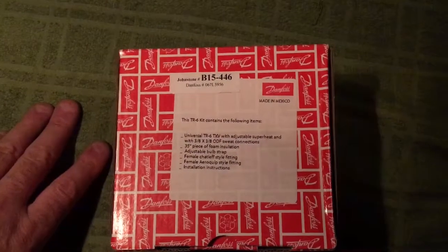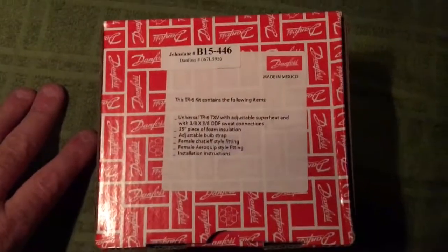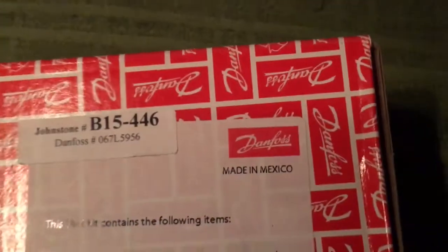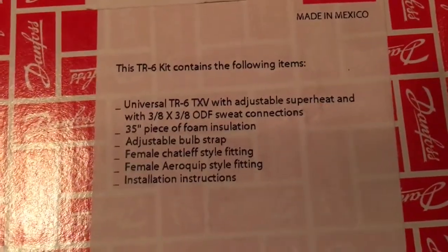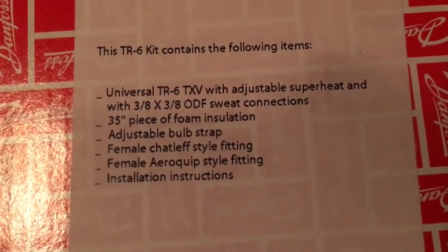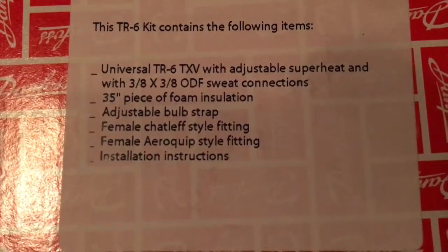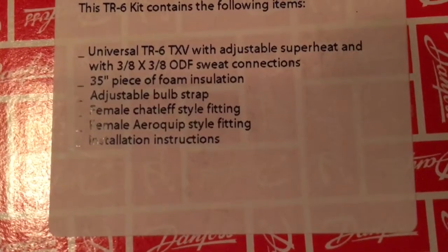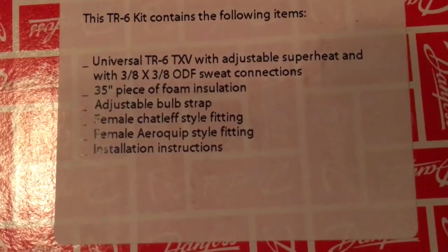For you guys that would like to get a little more performance out of the system, it's a nice looking valve. It's a Danfoss, made in Mexico. The TR6 kit contains the following items: universal TR6 TXV with adjustable superheat, 3/8 by 3/8 sweat connections, 35-inch piece of foam insulation, adjustable bulb strap, female Chatleff style fitting, and female Aeroquip style fitting.